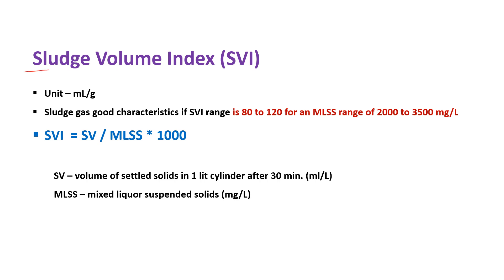The next is the sludge volume index (SVI), with units of milliliter per gram. The formula is: SVI = (volume of settled solids in a 1-litre cylinder after 30 minutes) divided by MLSS (mixed liquor suspended solids), multiplied by 1000. A sludge has good characteristics if the SVI ranges from 80 to 120, for a mixed liquor suspended solid range of 2000 to 3500 milligrams per litre.